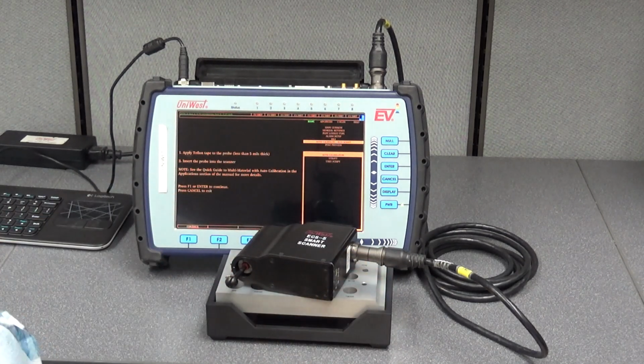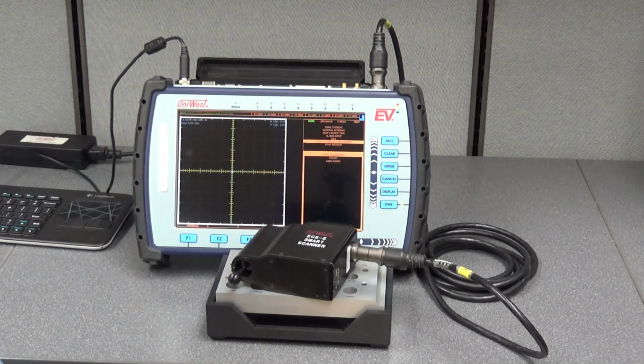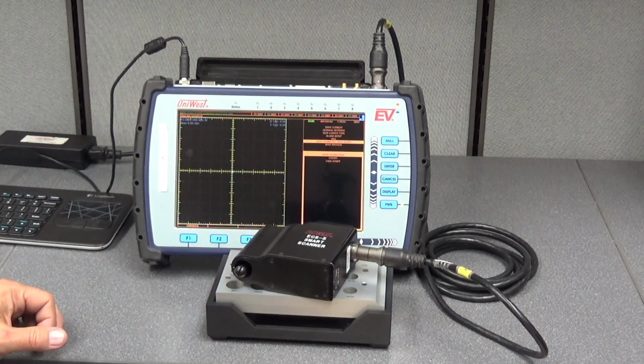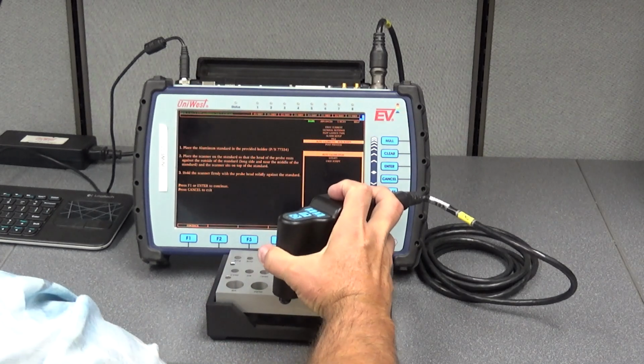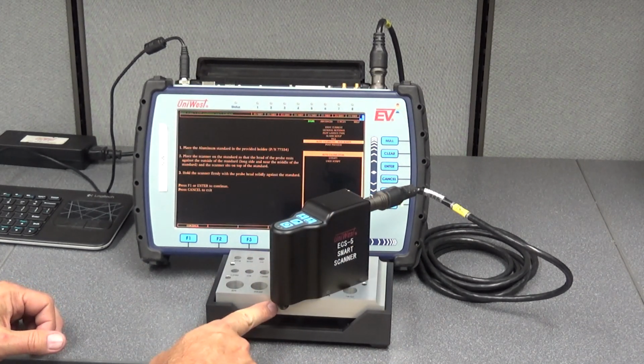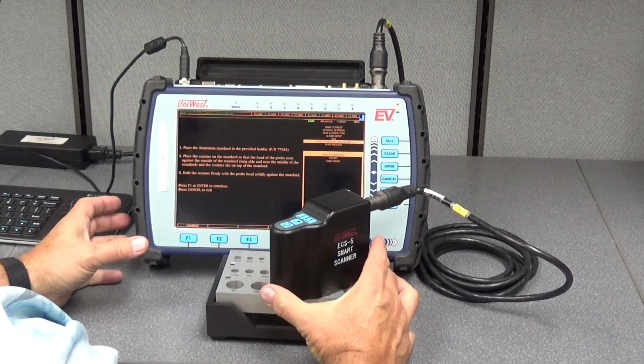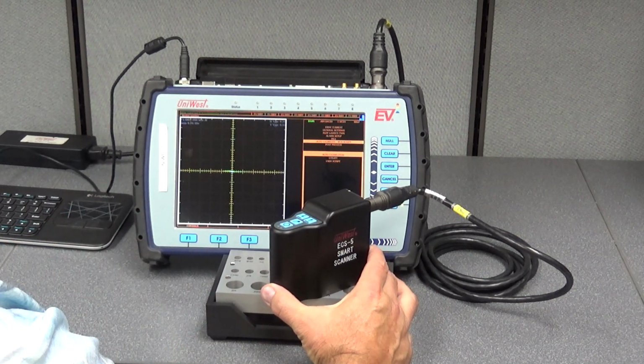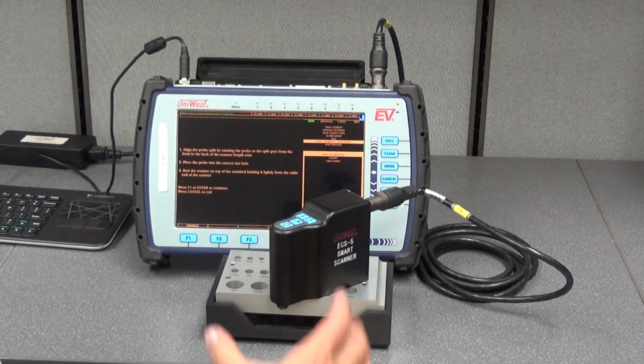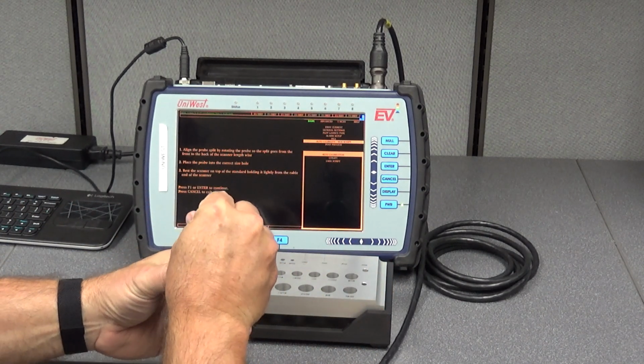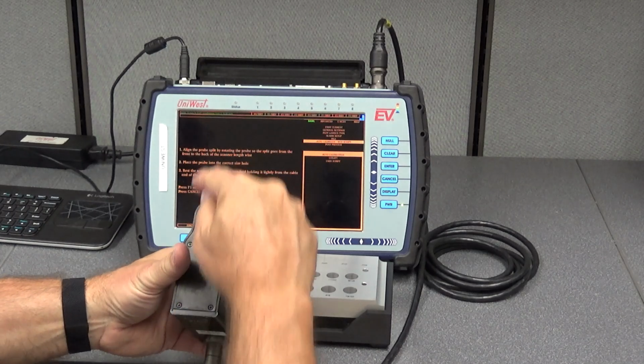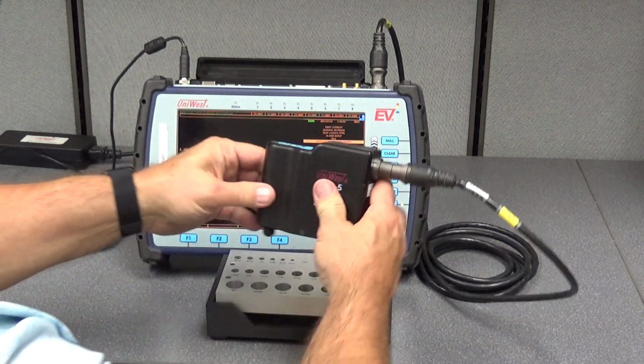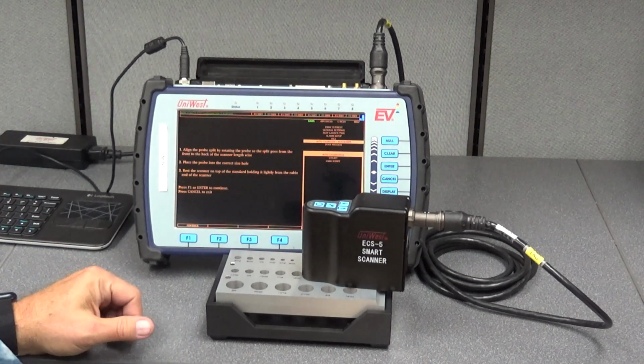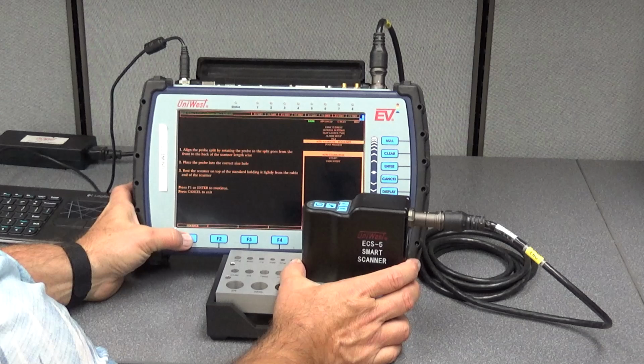Alright, probe is inserted. F1 to continue. Place the scanner on the top with the probe along the edge so we can set the lift off. So just hold on to it. Continue. Alright, so we've got the lift off. Next thing we need to do is align the probe split so that it goes along the long edge of the scanner. And then we're going to place it into the appropriately sized hole, in this case the half-inch diameter hole. And hit continue, F1 to continue.